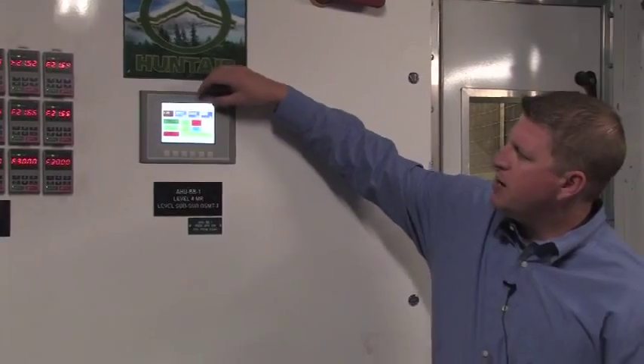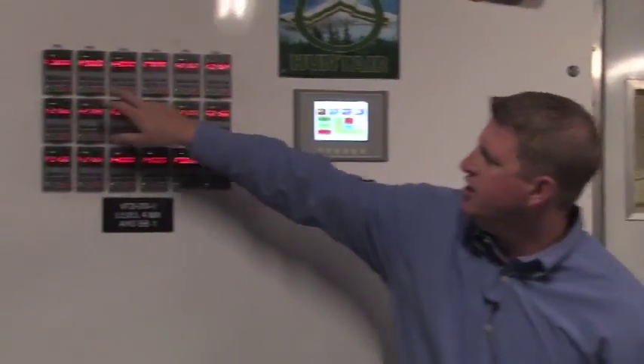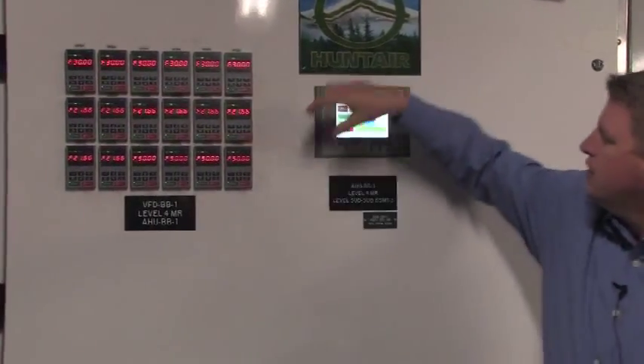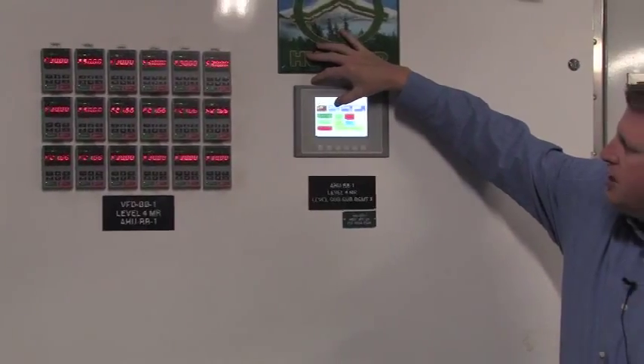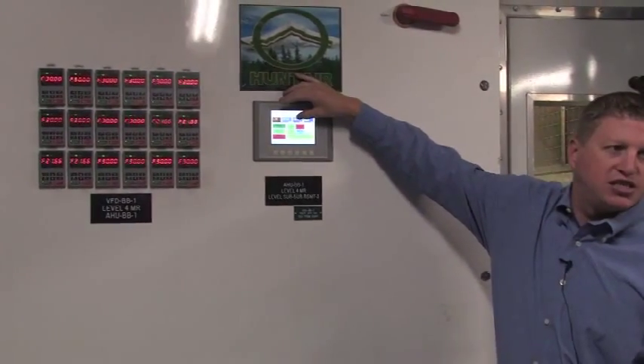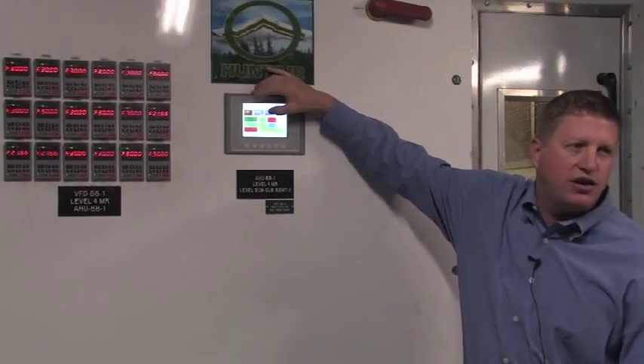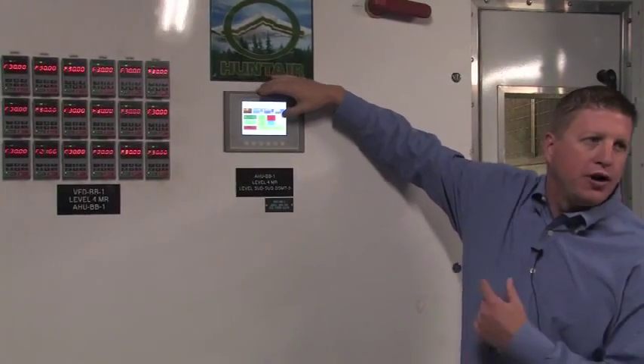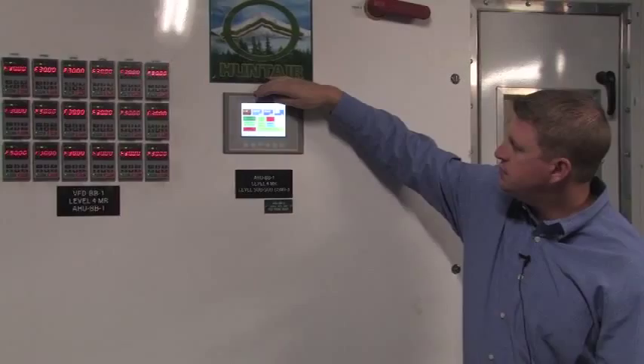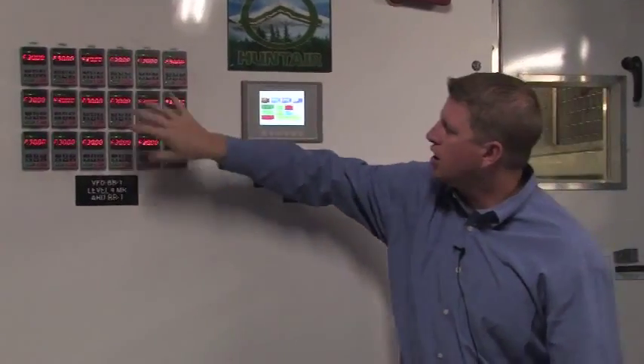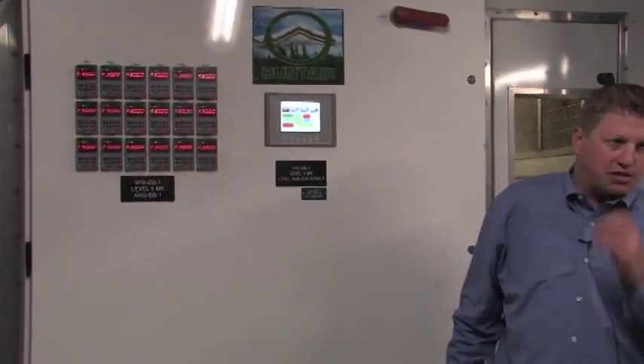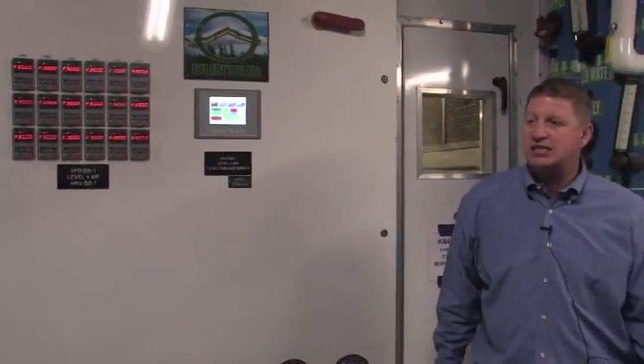So I gave it an input of 30 hertz, and you can actually see each one's going to 30. You'll see my CFM climb. This CFM is going to stay how it was because it's not what you're inputting. You're inputting hertz. So it's got it locked at 30 hertz and it'll level off probably somewhere around 30,000 CFM is my guess.